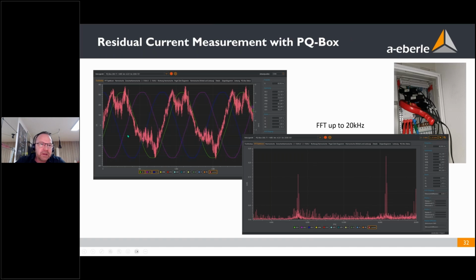In our software, we can also make snapshots online, offline, on the differential current here. This is a waveform. And if you have the waveform, in the software we also have the FFT up to 20 kilohertz, and we analyze how the current looks if the RCD is tripping. And here, as I told you, 8 and 16 kilohertz were the reason for it.